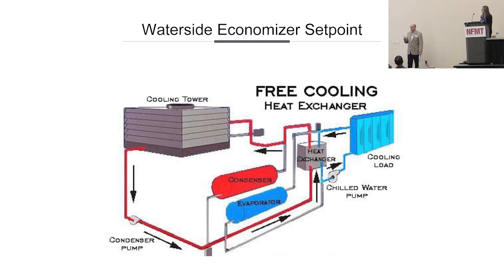Folks who are looking to do waterside economizing, if your cooling towers are concrete basin or concrete basin in ground, recognize that you have a heck of a heat sink to overcome before your system's going to want to drop into economizer mode, if it's going to do so at all, because of just the mass of that concrete. Depending upon your region, in a place like Alabama, yes, it does get cold in the wintertime. It can hit 10 degrees, things like that. But it does so very rapidly for a few days, and then you spring out. So something like a concrete cooling basin is never at the temperature for that economizer to really be able to come in on the water side, because the water will still hit the cold water basin, get warmed up by the earth, warmed up by the concrete, and then not operate the way you want it to. So that's the asterisk on that story.